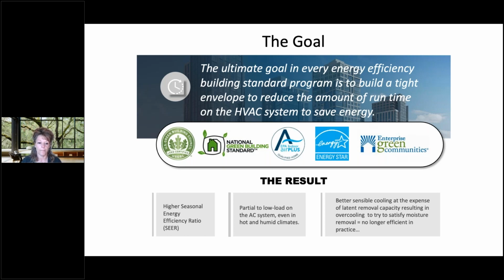So again, that higher seasonal energy efficiency ratio, so that higher SEER HVAC equipment, which is leading more to partial and low loads on our HVAC systems, even in hot, humid climates. And so we're also getting better sensible control with these higher efficient HVAC systems, because they're getting to that thermostat temperature more quickly.